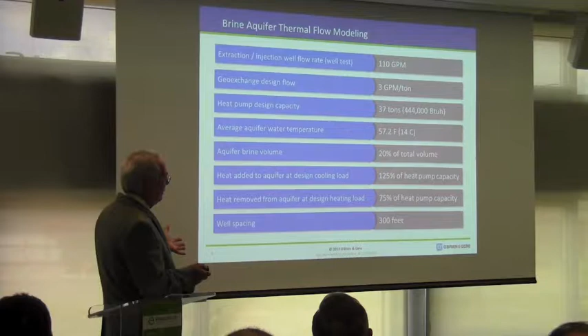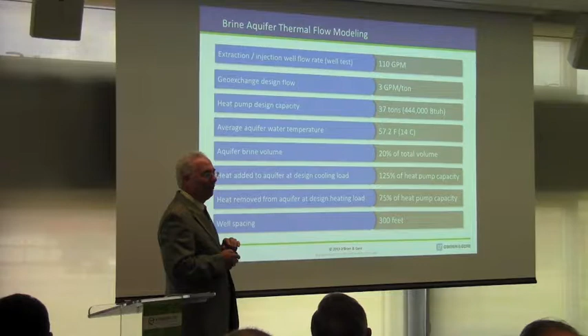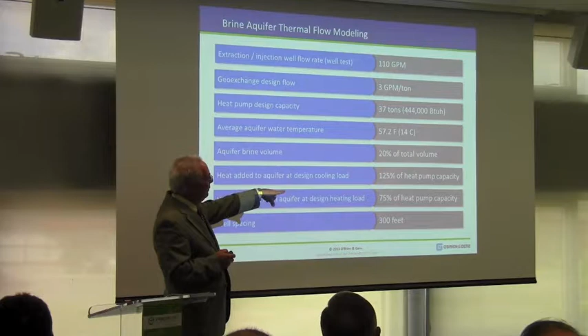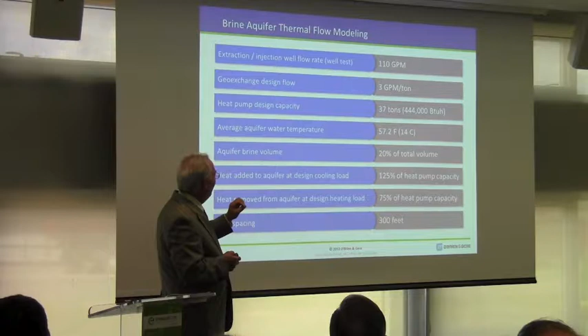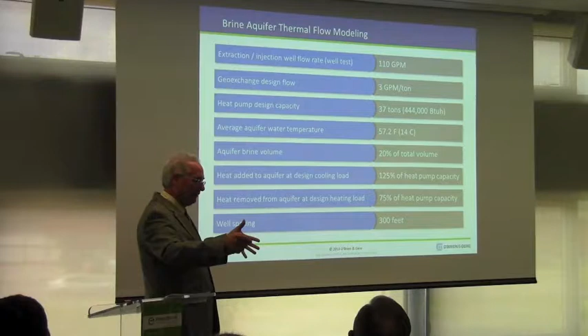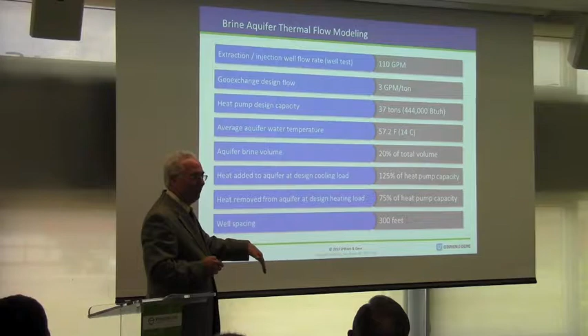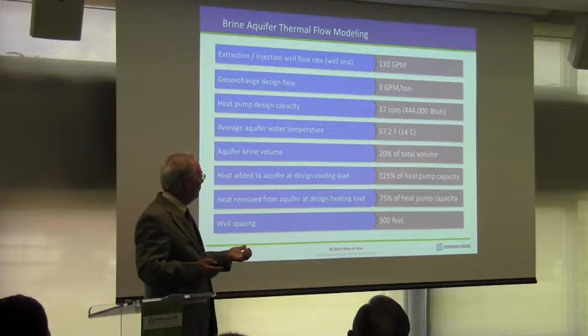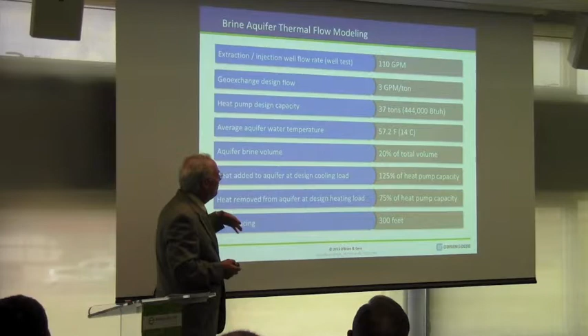So just like any type of refrigeration cycle, in the cooling season, we're going to be dumping 125% of the energy into the brine aquifer that we're taking out. The difference there is you get the compression of the compressor. In the heating season, we're going to be taking that heat out of the aquifer. Remember, the aquifer doesn't move, right? It's sitting there, as Bill said, it's stable. So the heat that you put in in the summertime is there in the wintertime to take out for heating. And that's how a heat pump system works, heating and cooling. So the heat that's removed is about 75% of the heat capacity at design.